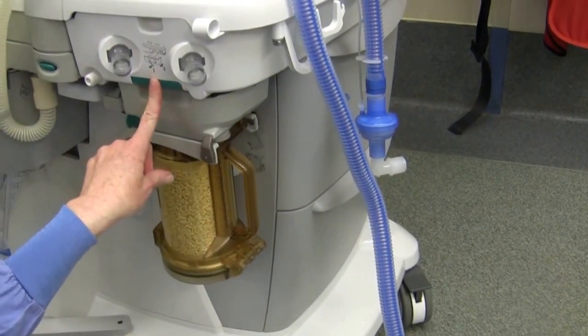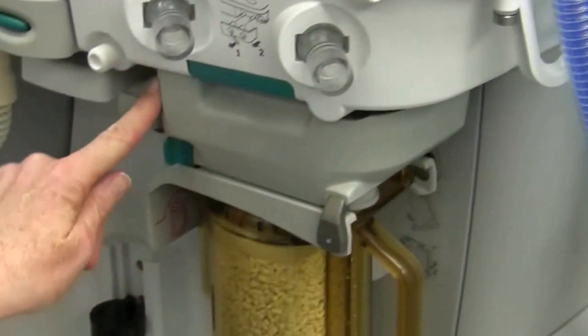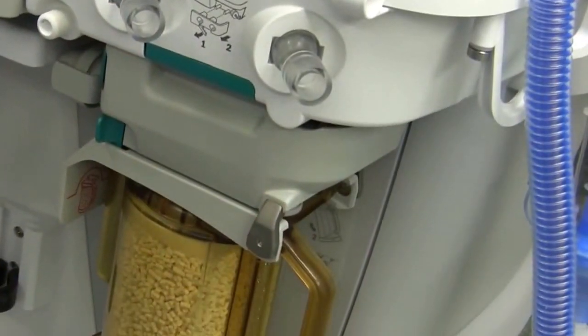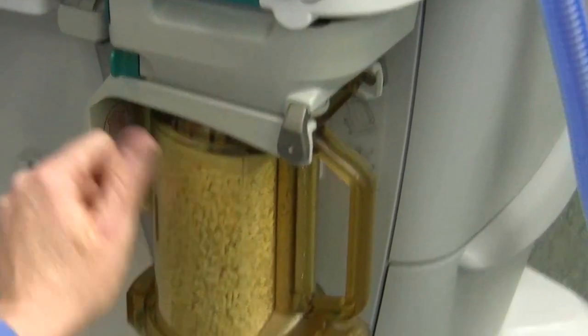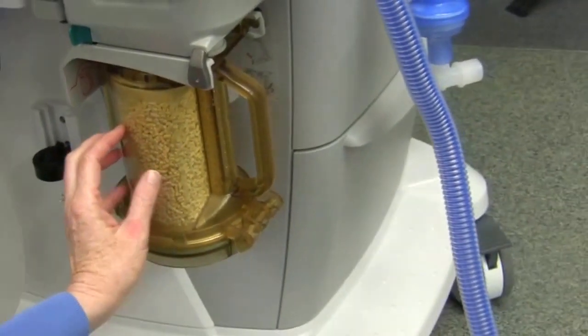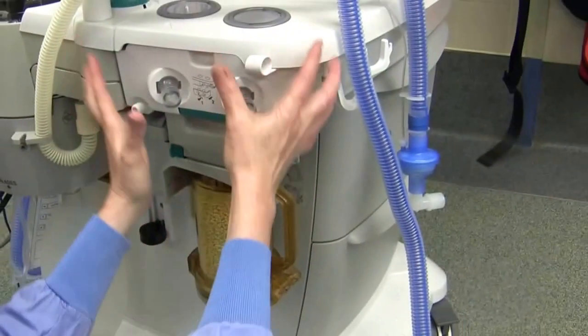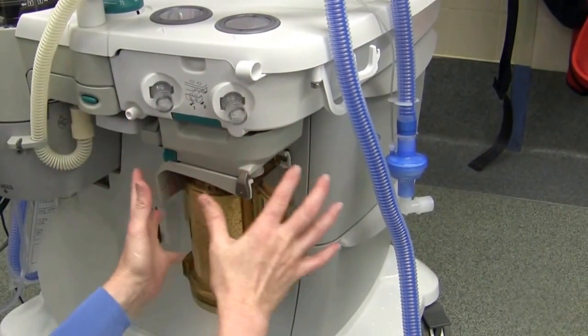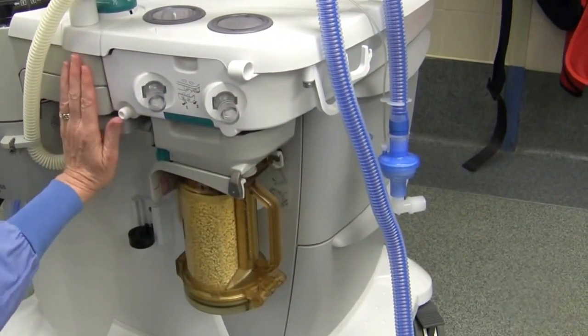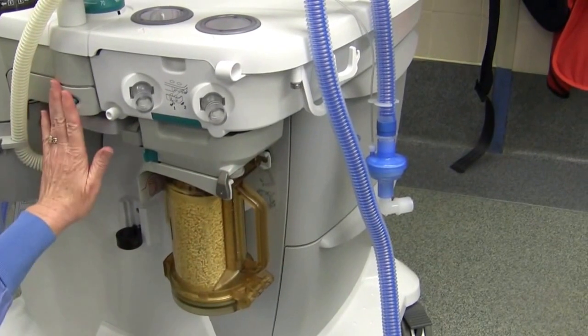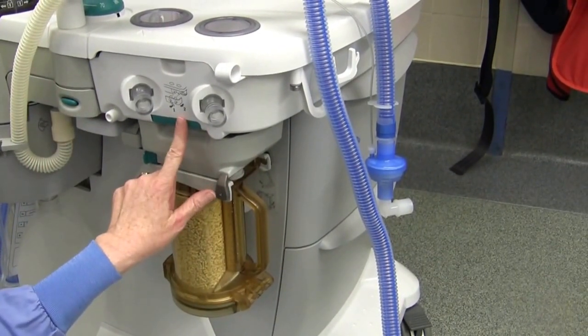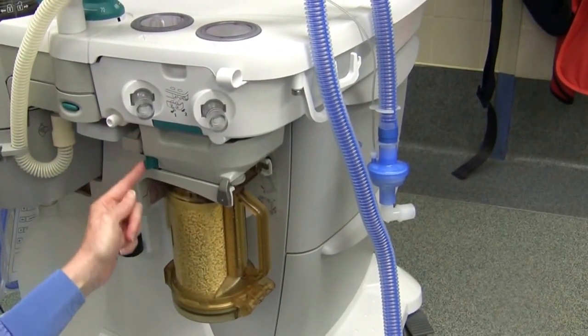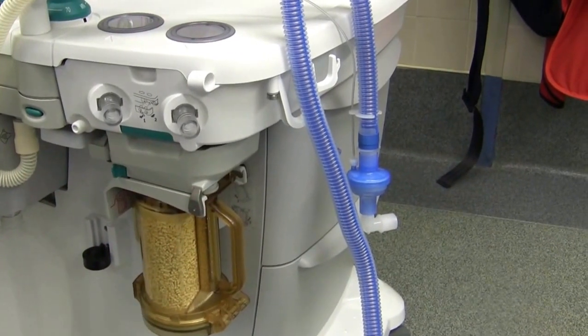So this button is for your flow sensors. This button here releases the whole unit. This one is the one if you want the easy change CO2. The button we don't want you to touch is this. If you hit this, the whole vent module comes out. It's not something you want to touch ever. That's usually ClinEd that has anything to do with that. So this is off limits. This is your calibration, and these two are involved with changing out your CO2.